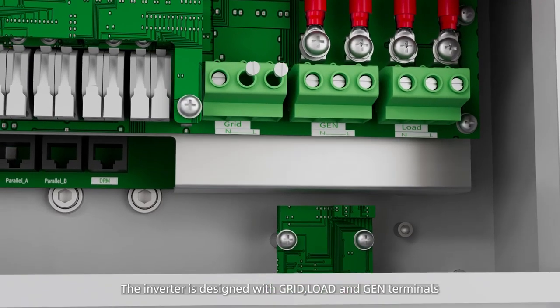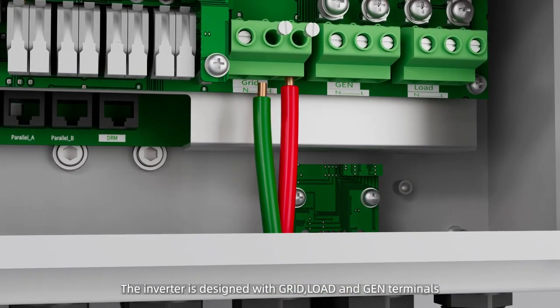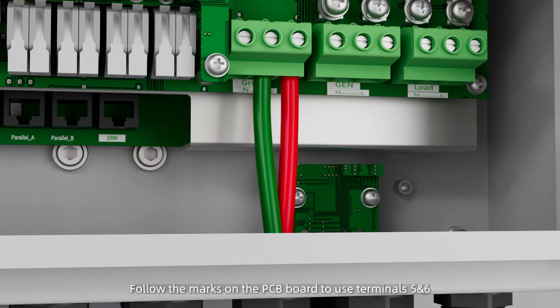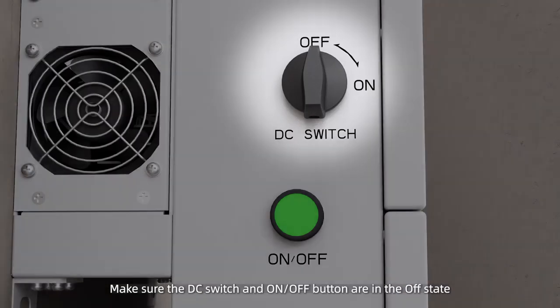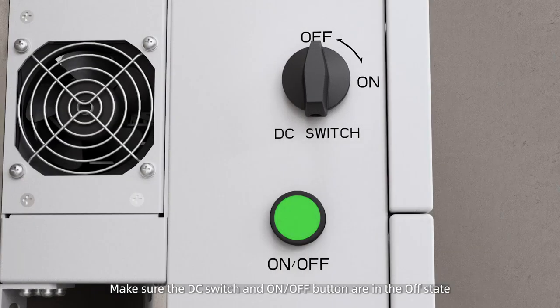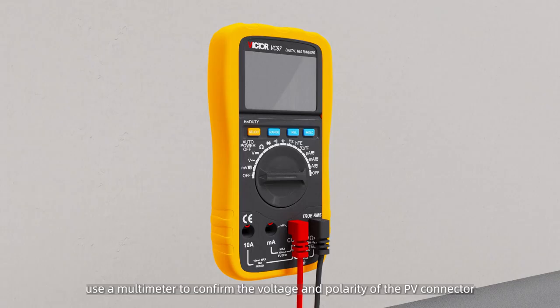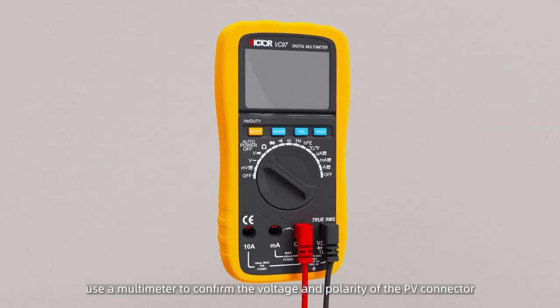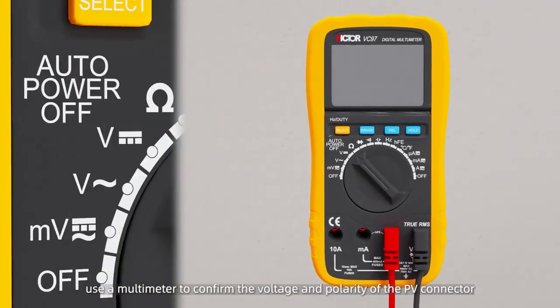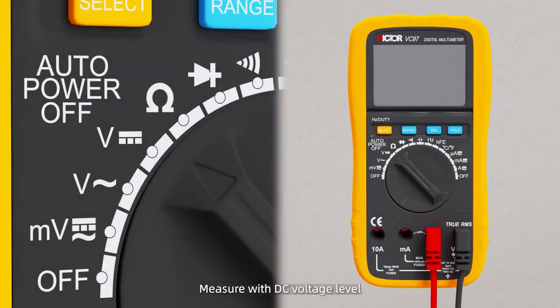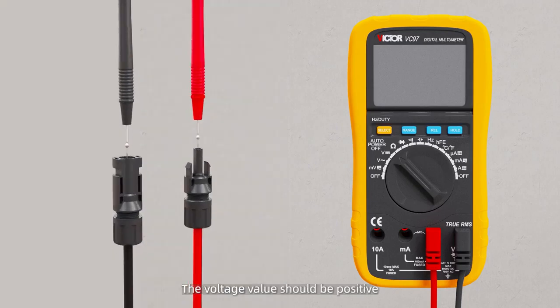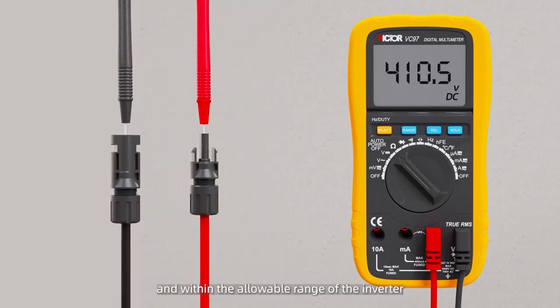The inverter is designed with grid, load, and gen terminals. Follow the marks on the PCB board to use terminals 5 and 6 to connect the wires of the CT. PV side connection. Make sure the DC switch and on-off button are in the off state. Use a multimeter to confirm the voltage and polarity of the PV connector. Measure with DC voltage level. The voltage value should be positive and within the allowable range of the inverter.